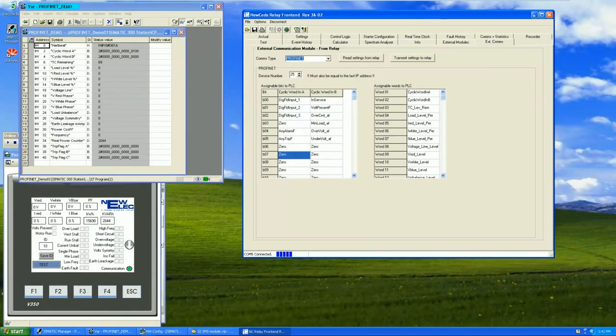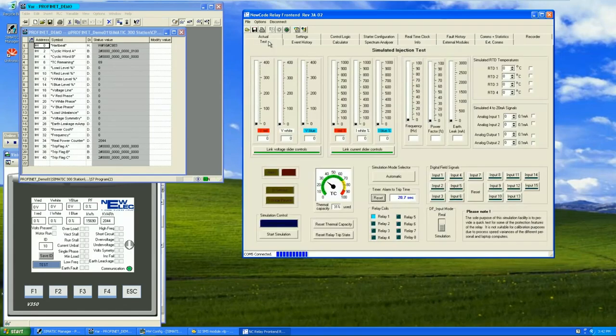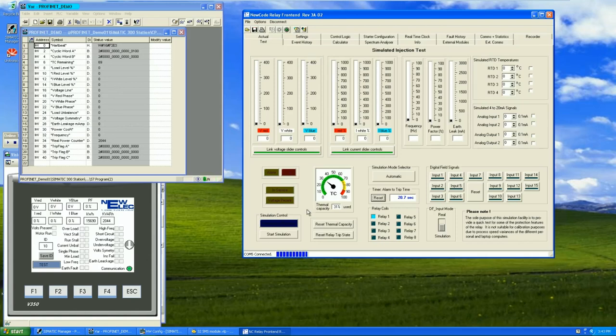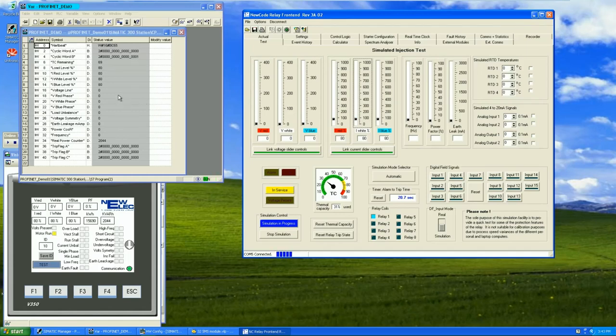A way to test the system integrator's PLC code without actually having the system there is using the test feature underneath the NewCode relay front end. The test feature will actually induce simulation values into the NewCode motor protection relay as if it was actually receiving information from a motor. To start up this process, just press the start simulation button. The simulation will now indicate it's in progress. When adding load, the relay will act as if it's got load and transmit the load values across to the SCADA.